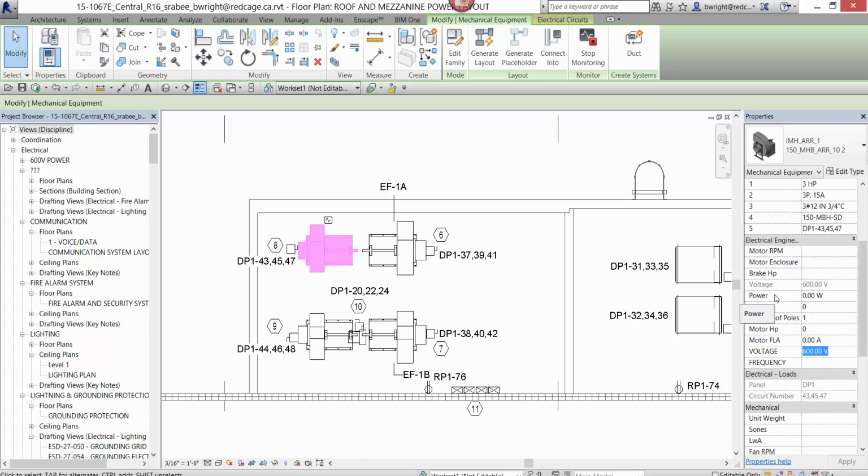So Autodesk has this shared parameter file, so if you download stuff from the Autodesk website, off Autodesk Seek, then you'll have the same ID numbers and everything will map up together. If not, then you may have to, like you're doing here, go into every family and add your voltage parameter, maybe call it voltage NA, and then remap their stuff to yours.